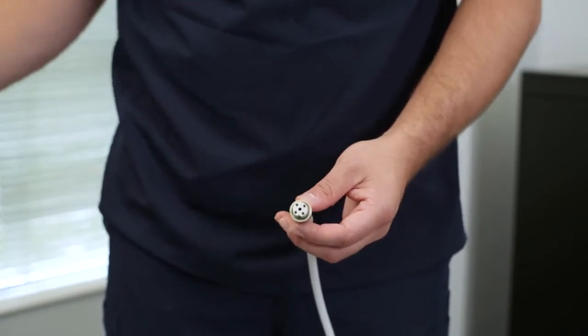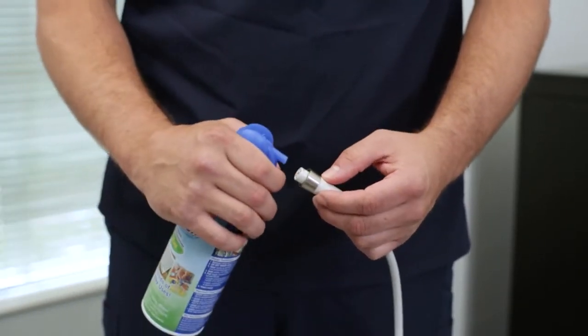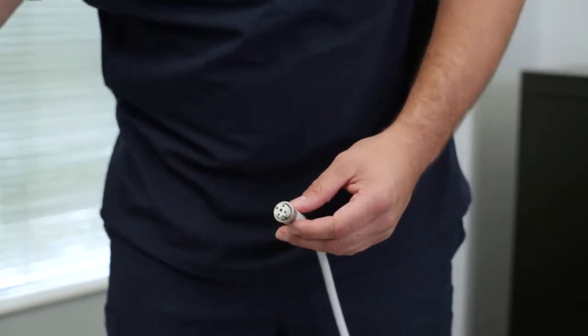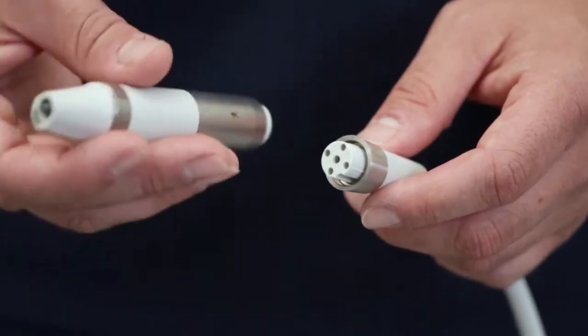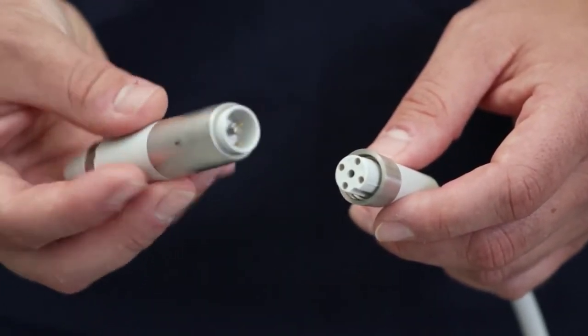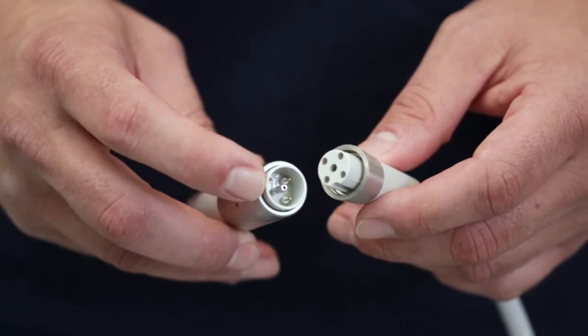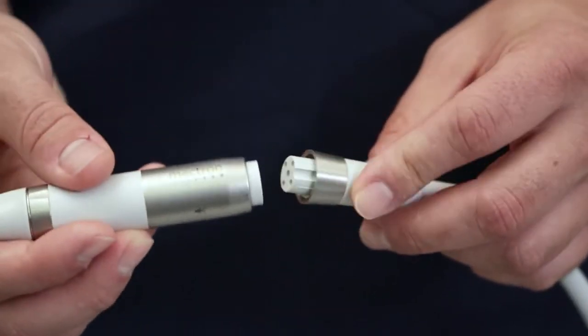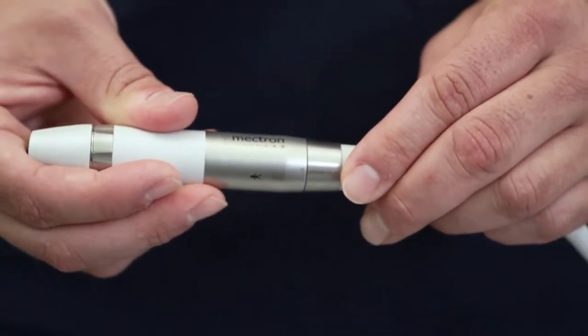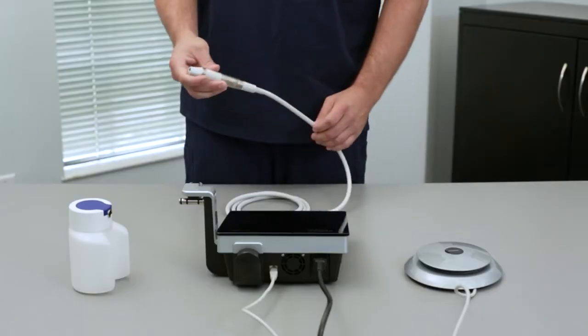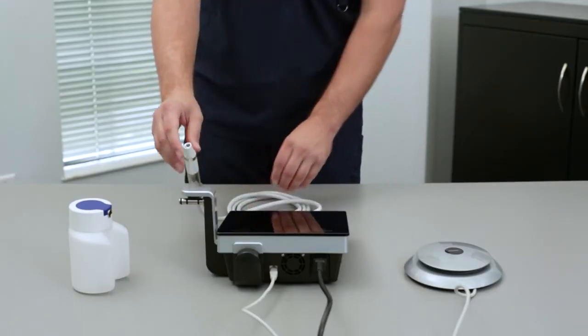The third item to plug in is the handpiece to its cord. To ensure that there is no residual moisture in the connector, spray compressed air into this connector. The handpiece is designed in such a way that you can only connect it to its cord in one specific orientation. The correct orientation is indicated by 2 alignment dots. Lastly, place the handpiece in its holder.